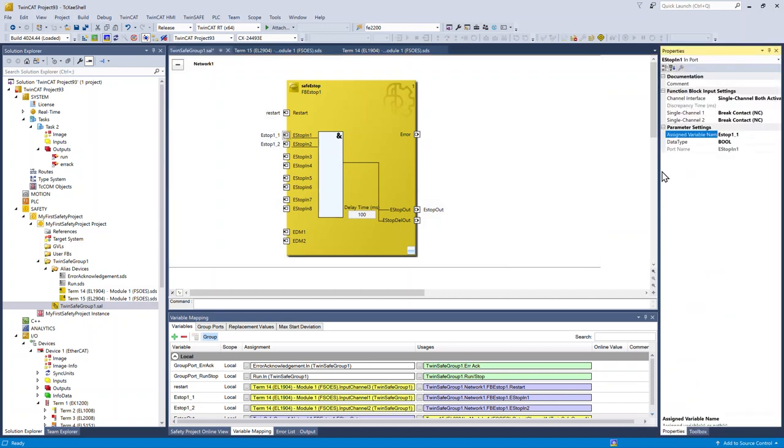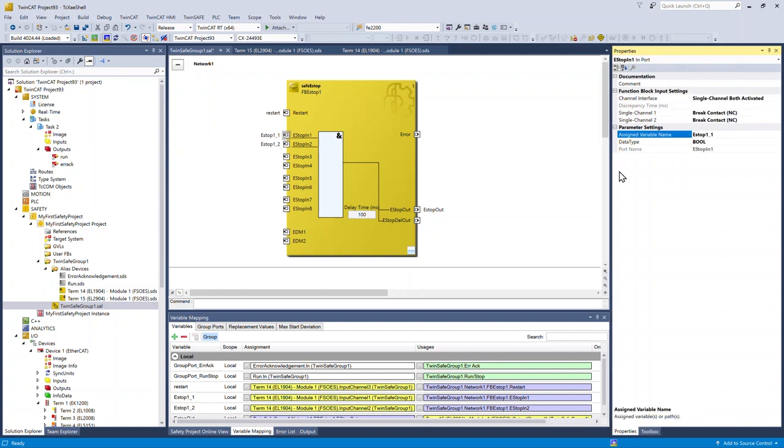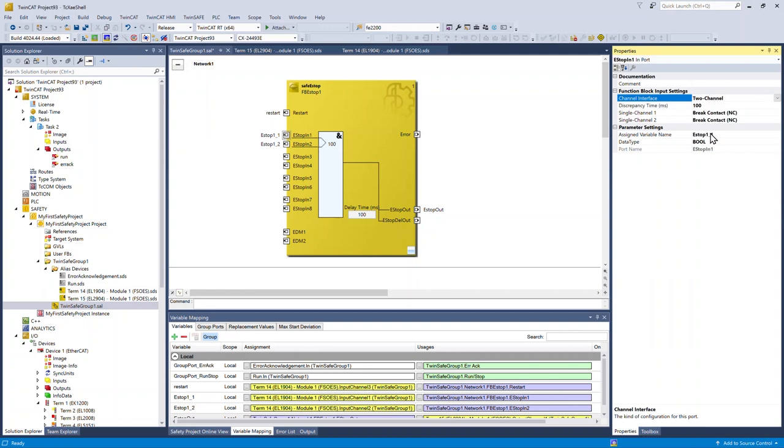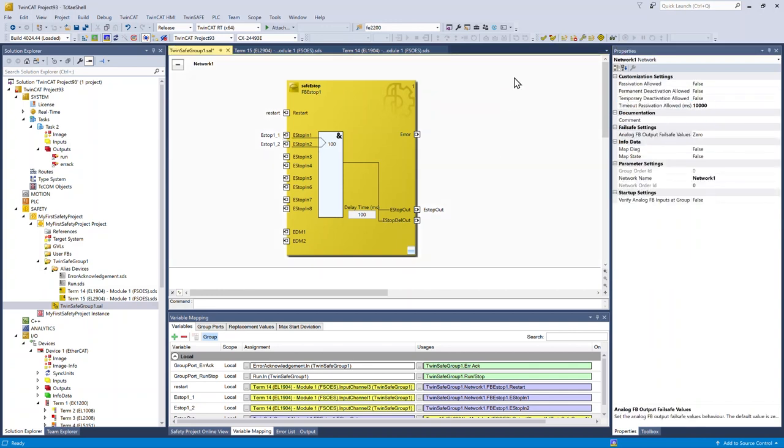Each one of the ports has settings that you can change specific to your application. In this case, since I'm using a two-channel e-stop, I want to change it to two-channel. Now we can identify discrepancy between the two channels.